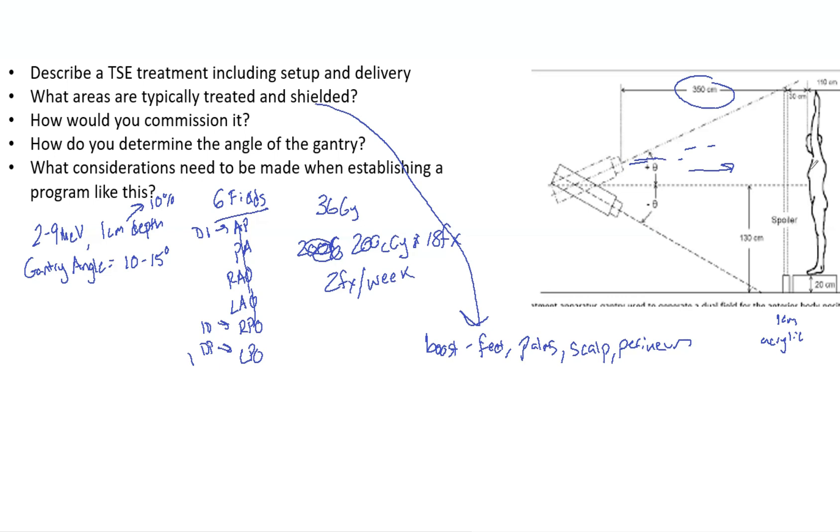When establishing a program like this, you want to use TLDs or diodes on the patient. That will give you a better idea of what dose they're getting, verifies your setup, and gives you something to document and peace of mind, knowing that each fraction they're getting approximately 200 cGy to their skin.